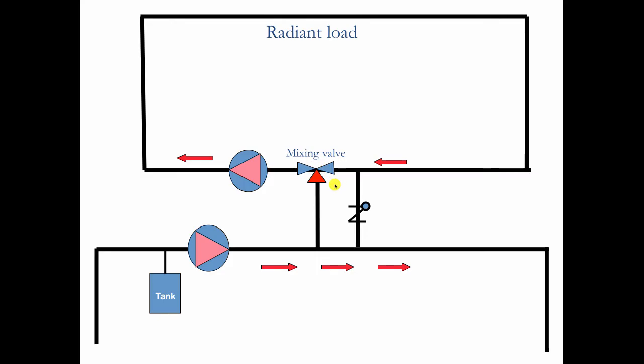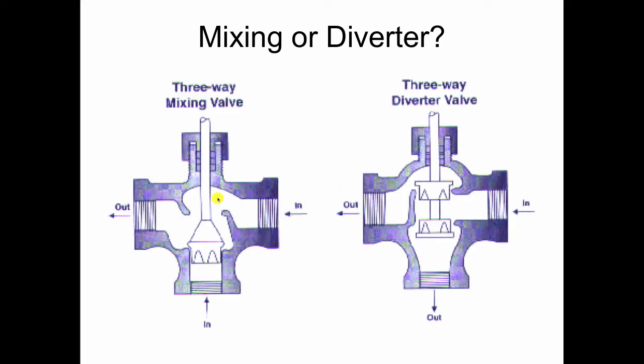So the way we get around that is, rather than use a three-way mixing valve, we're going to use a diverter valve. So this is a three-way mixing valve. It has two ways in, hot and cold, and one way out mixed. Two ways in, one way out.